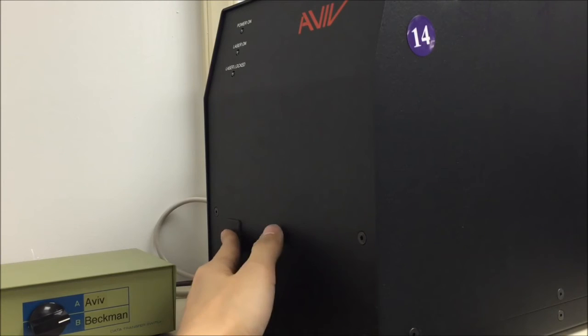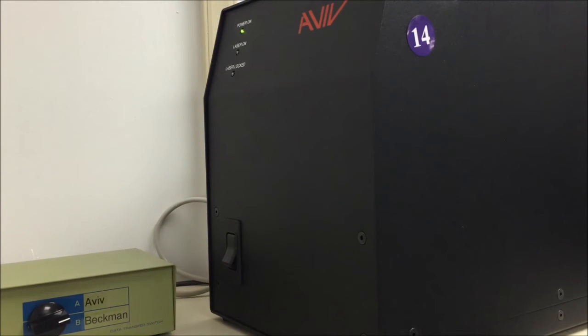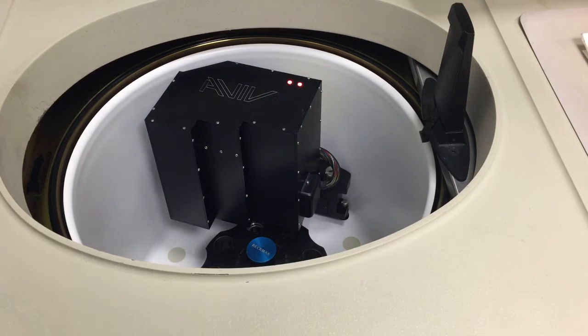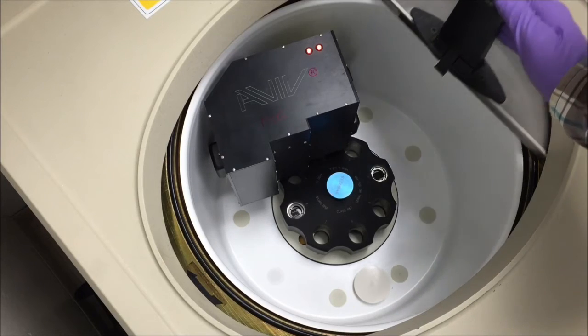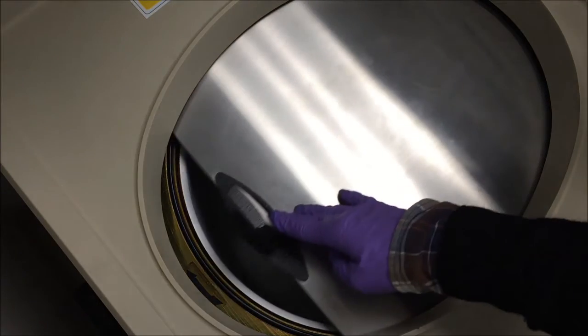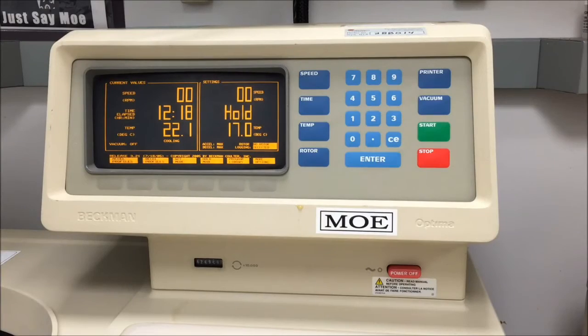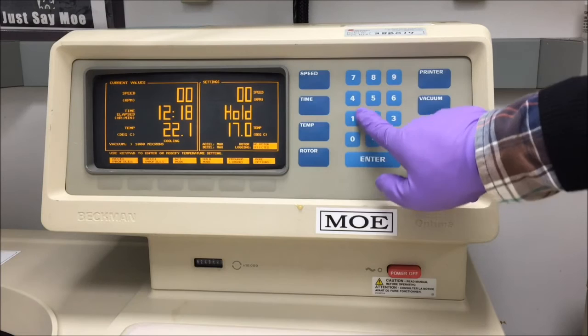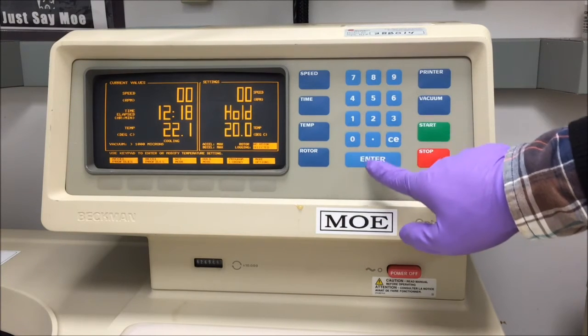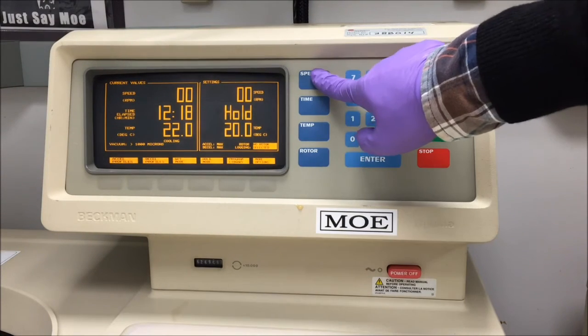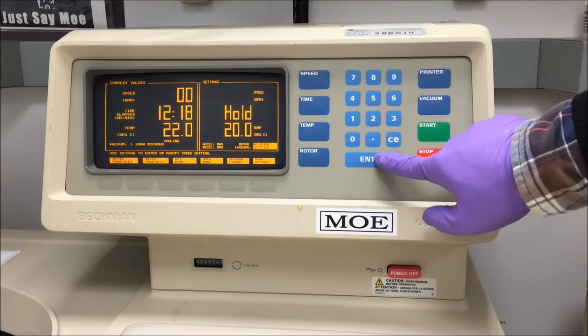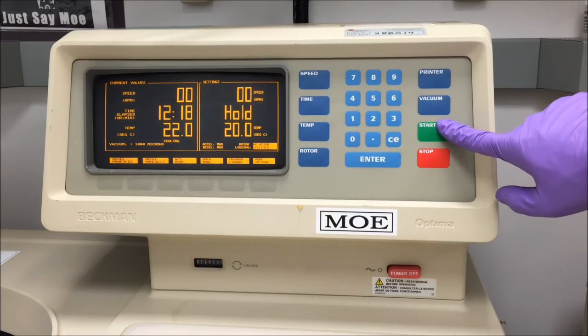Turn on the system box. Check the lights on the optics box. Two lights should be on. Close the chamber. Turn on the vacuum. Set the temperature at 20 degrees C and speed at 0 RPM. Click start. When the temperature reaches the target temperature, incubate the rotor in the centrifuge for 2 hours.